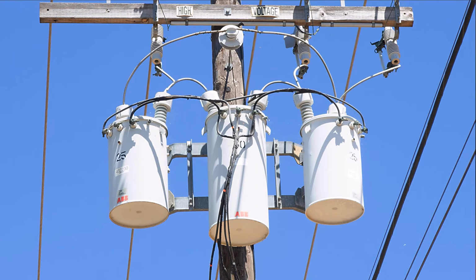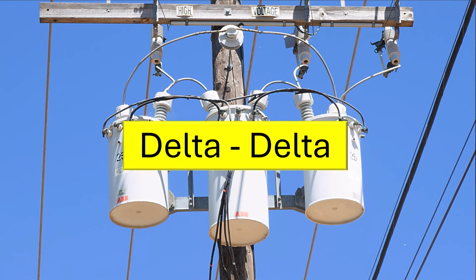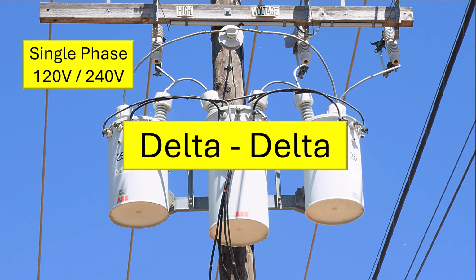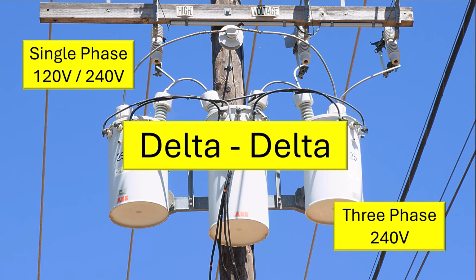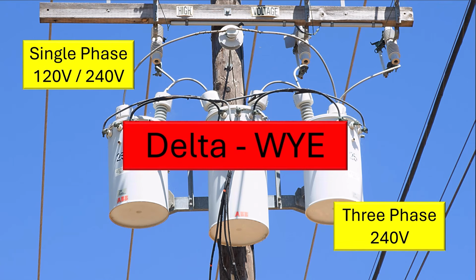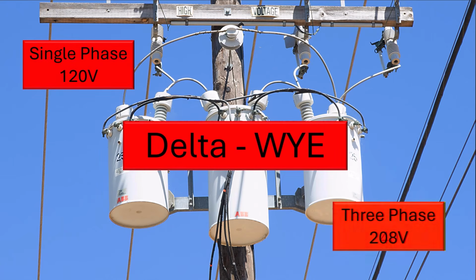Hey guys, in the previous video, we showed how you can use 3 single-phase transformers to create a 3-phase transformer bank. Connected in a delta-delta configuration, this transformer bank provides single-phase 120 volt and 240 volt power, as well as 3-phase 240 volt power. In this video, we're going to show how you can connect the same 3 transformers in a delta-wye configuration to produce single-phase 120 volt power and 3-phase 208 volt power. We'll then talk about what this type of transformer is used for.